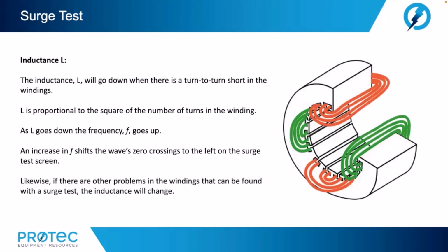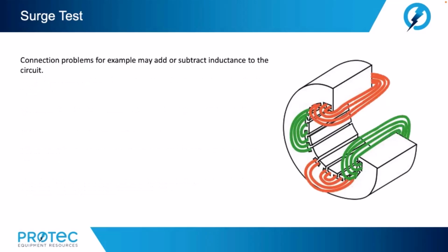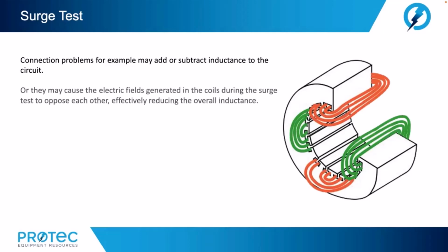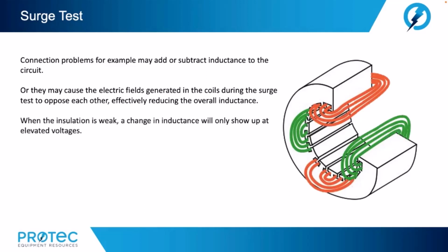Likewise, if there are other problems in the windings that can be found with a surge test, the inductance will change. Connection problems, for example, may add or subtract inductance to the circuit. Or they may cause the electric fields generated in the coils during the surge test to oppose each other, effectively reducing the overall inductance. When the insulation is weak, a change in inductance will only show up at elevated voltages.